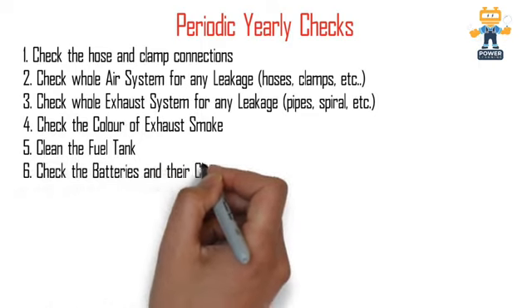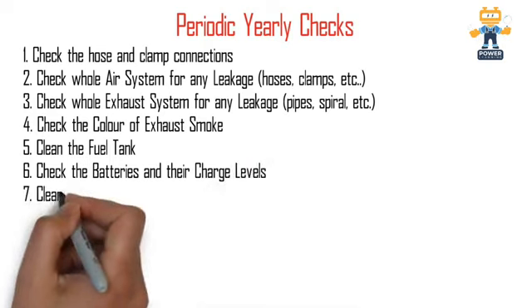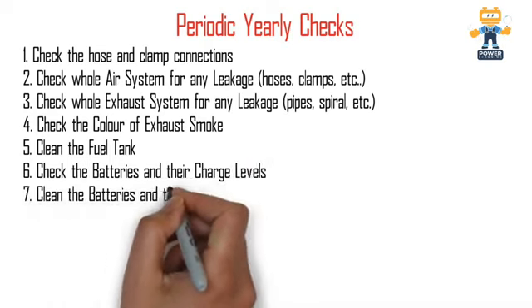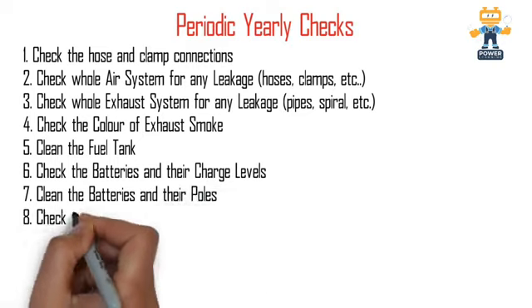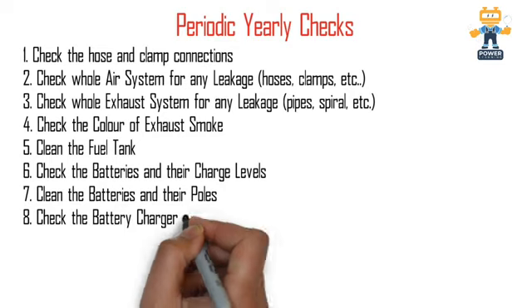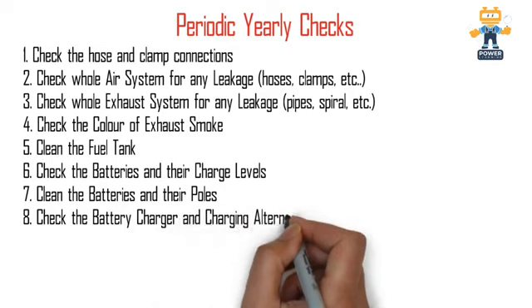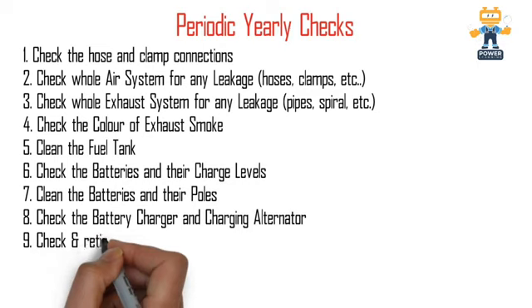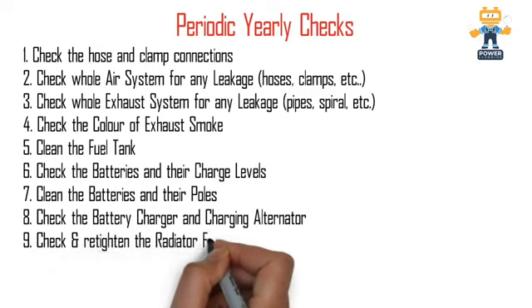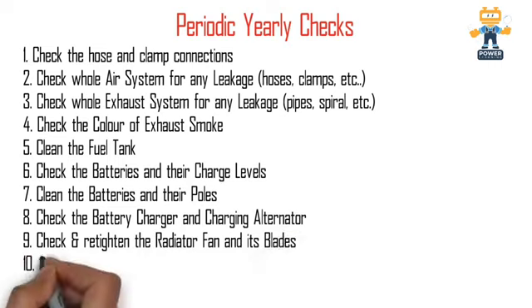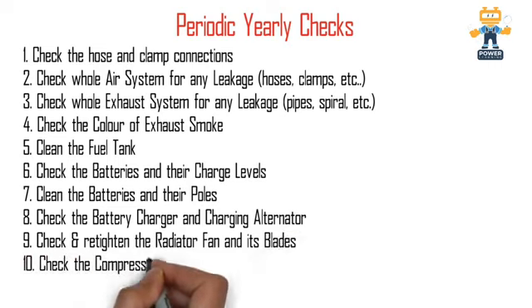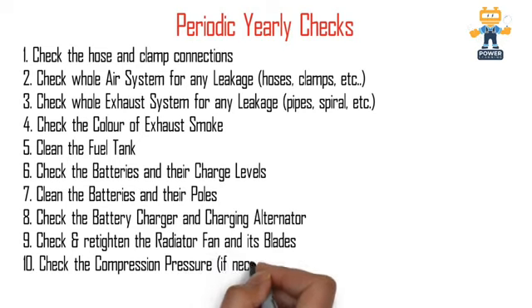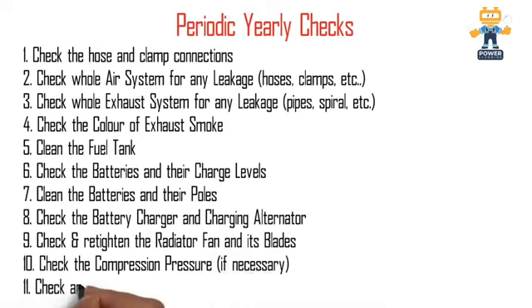Check the color of the exhaust smoke when the generator is running. If there is any different color, you have to check with your mechanical team. Clean the fuel tank. Check the batteries and their charge levels, clean the batteries and their poles, and check the battery charger and charging alternator: what the charging voltage is and how the charging alternator works. Check and retighten the radiator fan and its blades also. This is very important, as sometimes it gets loose and will damage the radiator. Number 10 is check the compression pressure if necessary. And number 11, check and clean all the oil pan breather hoses. It's very important.